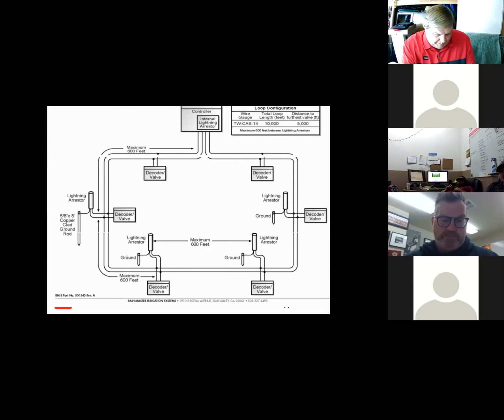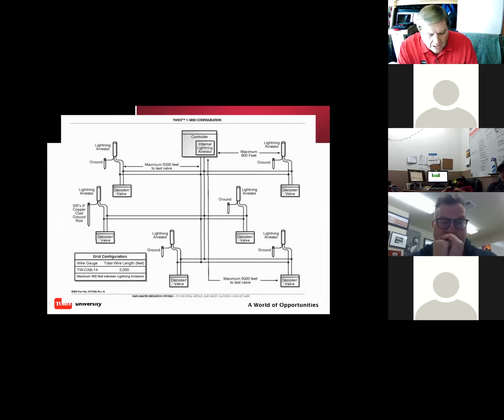In some systems, you can loop it. I don't recommend it, but you can loop it and get a little further distance out of your 2-wire path because of the power shared. But either way, you've got your system, you've got your decoders, and then you have your surge device, if we call it a lightning arrestor device, and a ground rod. Where you put the ground rods is very specific to brand, but in general, they're approximately 600 feet apart. And don't put the ground rod in the same valve box as the decoder. You want to move that ground rod away from the 2-wire path, and we'll get into grounding in just a few moments. But that just gives you an example of where the decoders go and where to put the lightning arrestor or the ground rod.